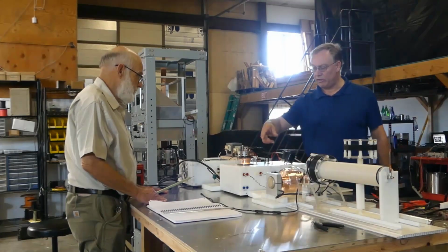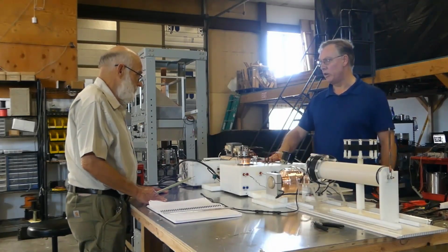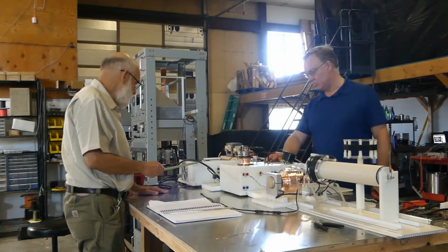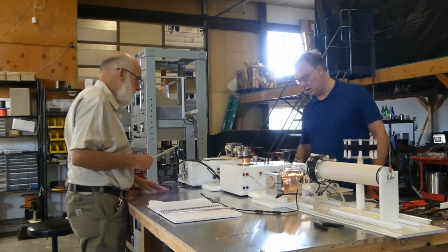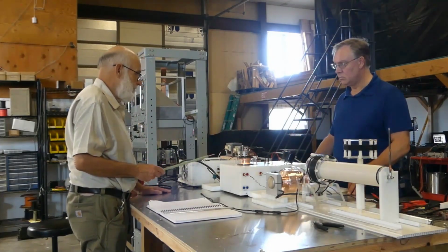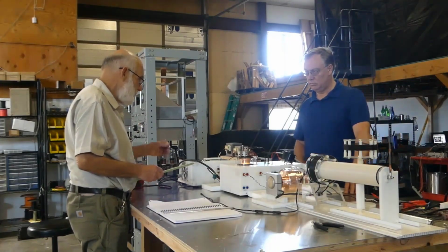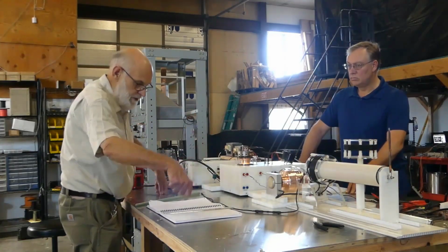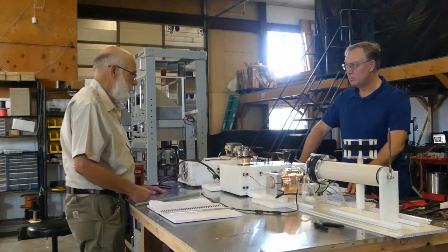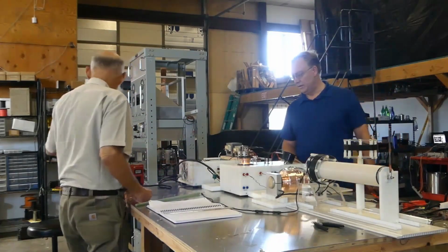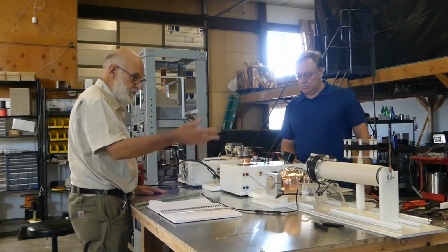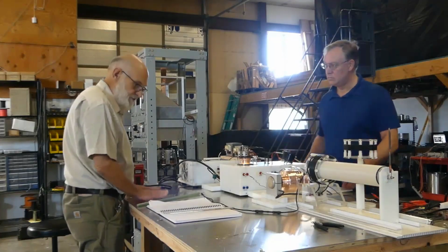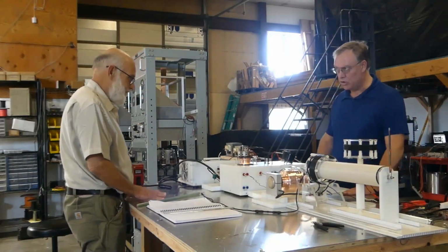So these RF currents, when they bypass, they just go straight down to the earth? Well, in this case, there's no earth here. There's just over here. So you have to think in terms of neutrals and then the common point, which is then connected to earth. You can't just start connecting things to ground here. It doesn't work like that. There is no ground. You have 100 ohms of impedance between this and ground, maybe even more. If it's the right length electrically, there could be no conduction whatsoever. There's no such thing as ground, unless you have this. This is our virtual ground plane.